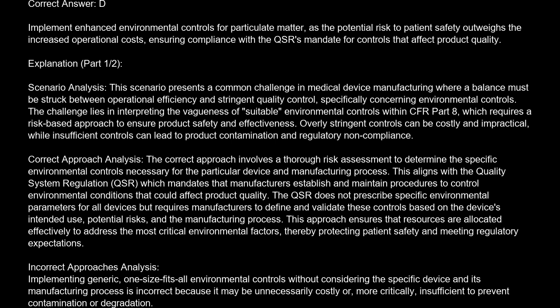Correct approach analysis. The correct approach involves a thorough risk assessment to determine the specific environmental controls necessary for the particular device and manufacturing process. This aligns with the Quality System Regulation, QSR, which mandates that manufacturers establish and maintain procedures to control environmental conditions that could affect product quality.